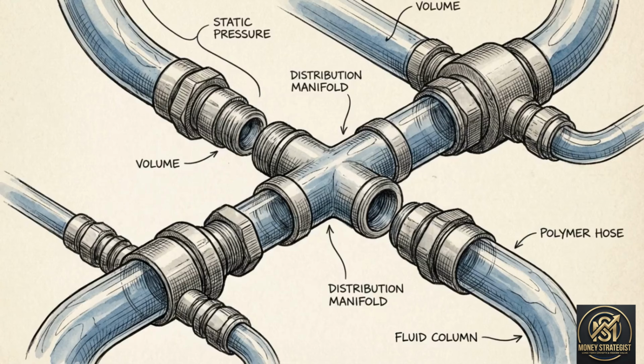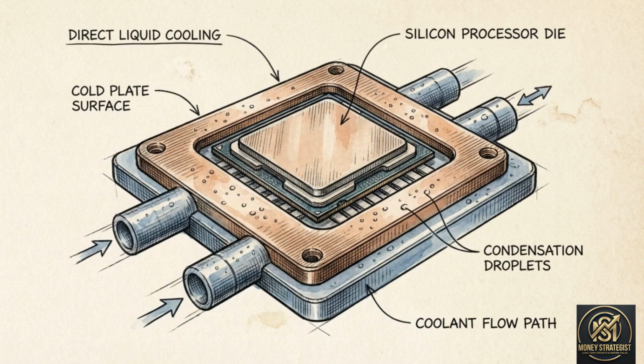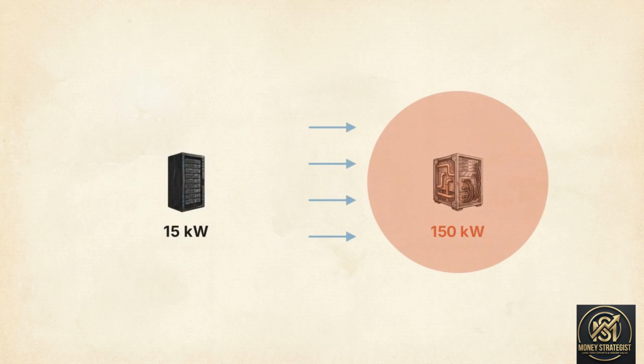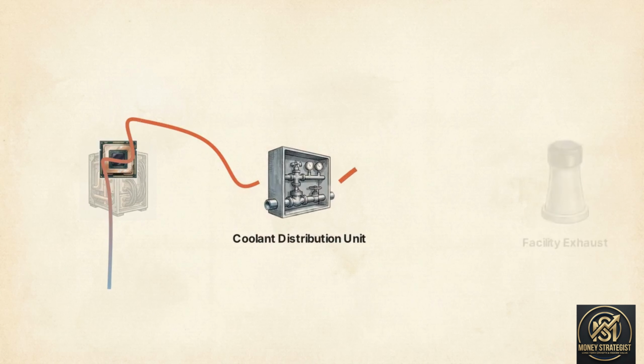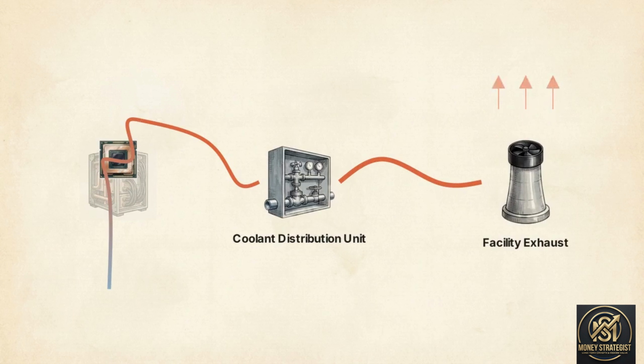At 150 kilowatts, air is an ineffective conductor of heat. Pushing cold air over the chips is insufficient for these thermal loads. The viable engineering solution is direct liquid cooling. Facilities must pump massive flow rates of warm water, between 15 and 25 degrees Celsius, through cold plates attached directly to the silicon. The liquid absorbs the heat, preventing thermal throttling and equipment destruction. While liquid captures the heat efficiently inside the server chassis, that thermal energy does not disappear. It must be rejected from the building. The heated liquid cycles through a coolant distribution unit, which transfers the thermal load out to the facility's exhaust systems.